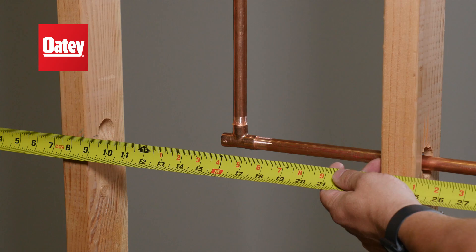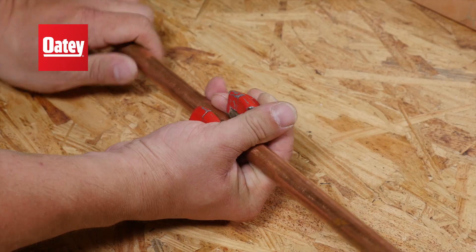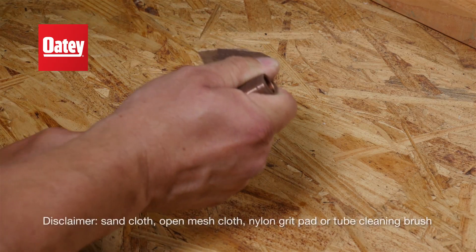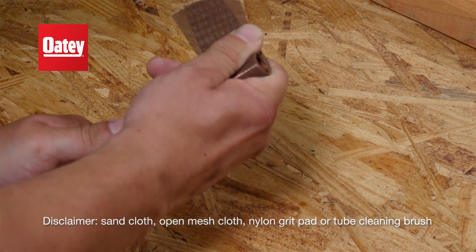First, measure and cut copper pipe to the desired length. Deburr and clean the outside of the pipe ends with Oatey Sand Cloth, Mesh, or Grit Pad.